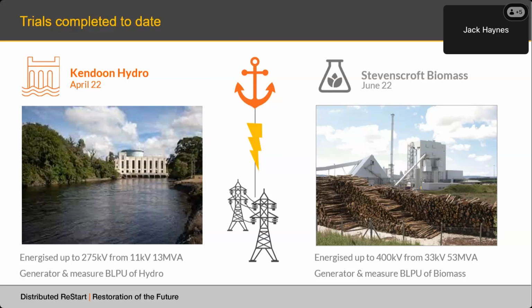Then similarly, later on in 2022, the Stevenscroft biomass generator was utilised to energise all the way up to 400 kV. This time it was a 53 MVA unit connected at 33 kV. And again, the block load pickup capability of the asset was measured there. So up to this point, we demonstrated the ability of a series of synchronous generators to energise all the way up to the highest transmission level that we have in the UK.